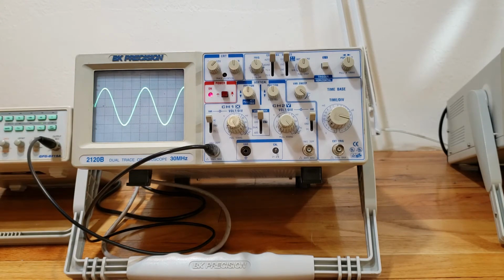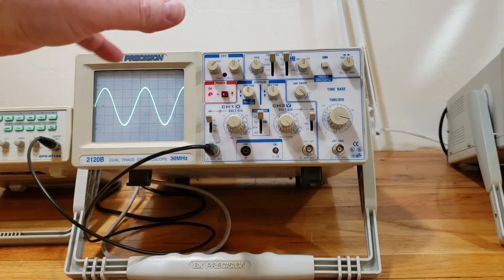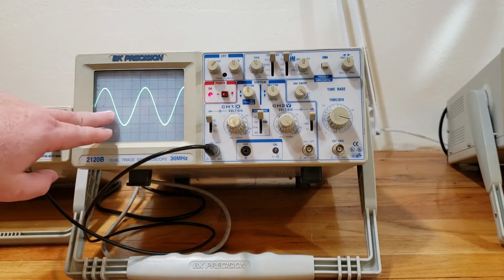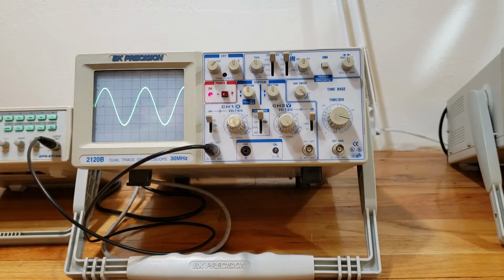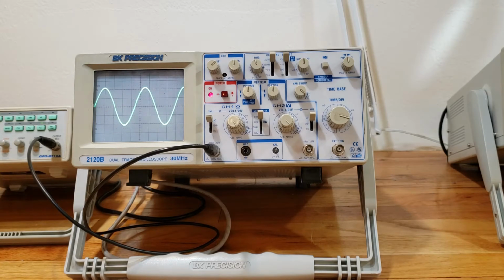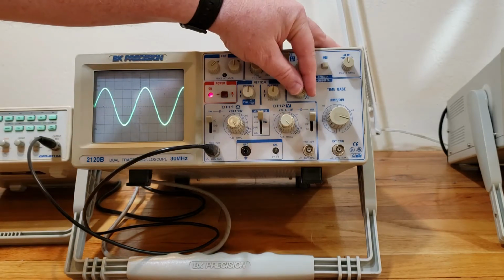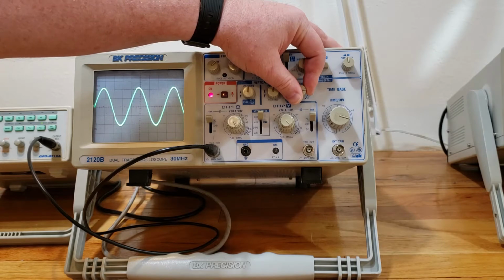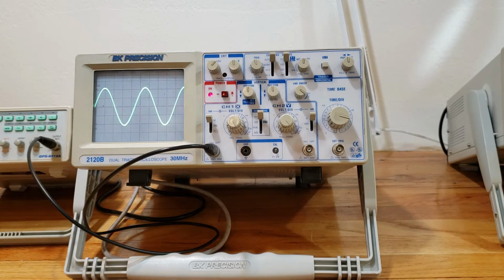To the right of the vertical position knob for channel 2, oh, by the way, the vertical position knob for channel 2 also has a pull feature. We would use that when using the XY function. The variable sweep knob, which is this knob right here, is used for calibration. For example, the signal that's coming in here has a specific frequency that's set by its source. If I know that specific frequency, I can use the variable sweep to adjust so that I get exactly that frequency, so that I would have a more accurate measurement.